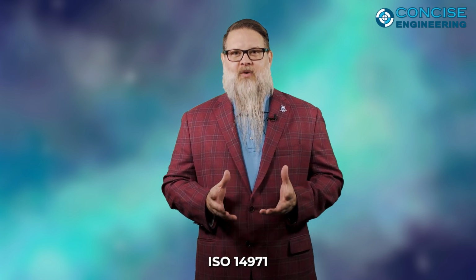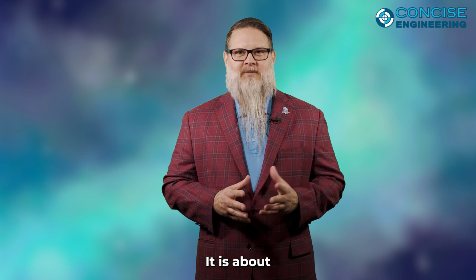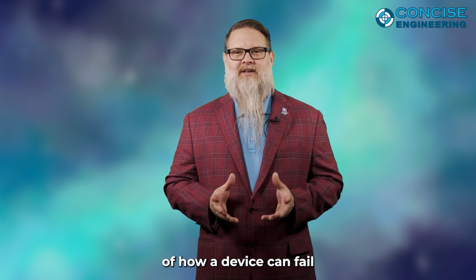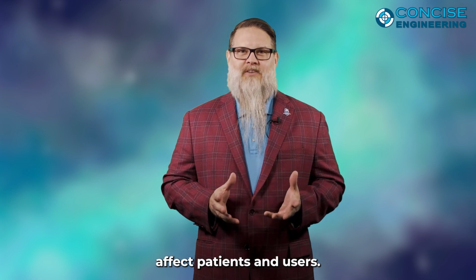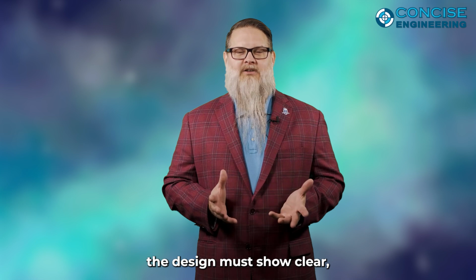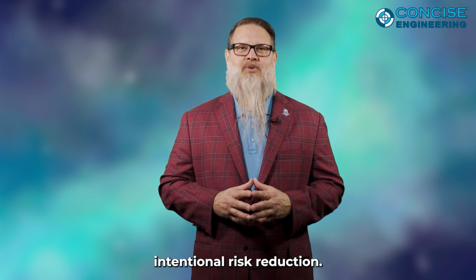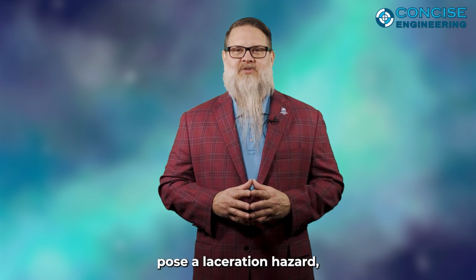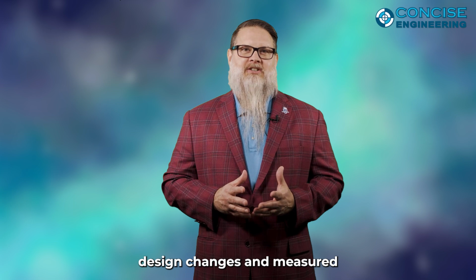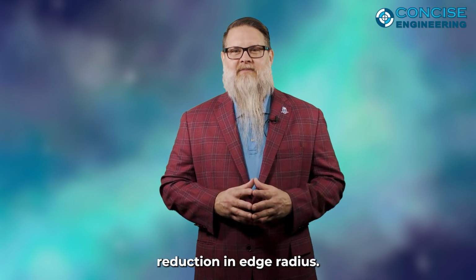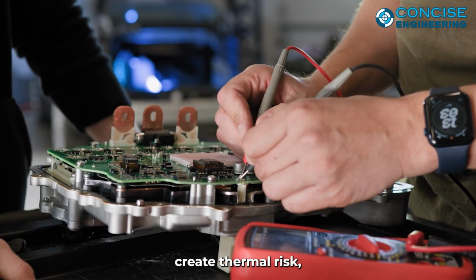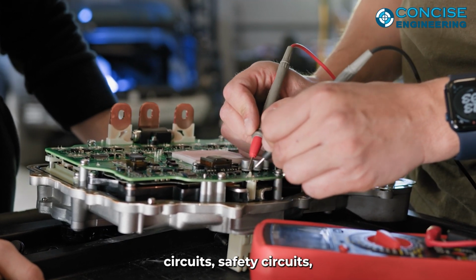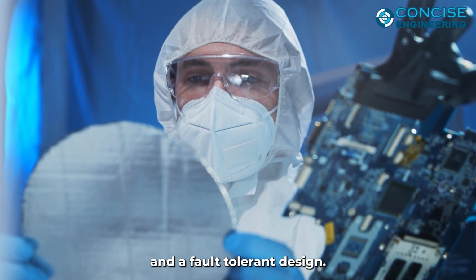ISO 14971 is not about creative brainstorming. It is about systematic identification of how a device can fail and how those failures affect patients and users. From there, the design must show clear, intentional risk reduction. If sharp edges pose a laceration hazard, you need mechanical design changes and measured reduction in edge radius. If battery faults create thermal risk, you need thermal cutoff circuits, safety circuits, and a fault-tolerant design.